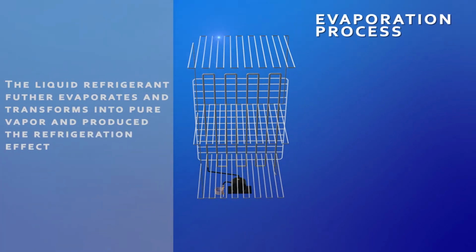During the evaporation process, the fluid expands and absorbs sensible heat from the inside of the refrigerator or freezer. Similar to condensers, there are static and forced draft evaporators. Static evaporators work through natural convection as well as conduction heat transfer mechanisms.